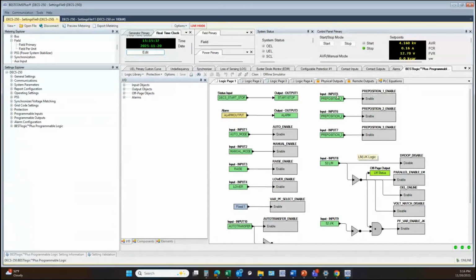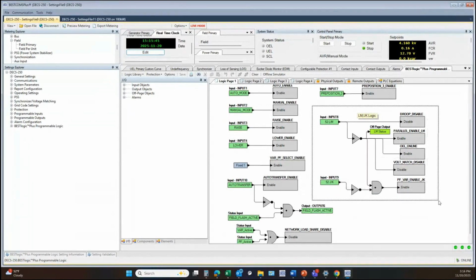You may choose to have something set up logic to trigger a preposition other than a contact input. This LMJK logic is based upon our DECS 200 design, how those 52LM and 52JK inputs actually operated. So our default logic is looking for a B contact from your breakers. So when the breaker is closed, the B contact will actually be open, and vice versa. So once the generator breaker closes, the 52LM input should open, and that will enable our paralleling through this NOT gate.